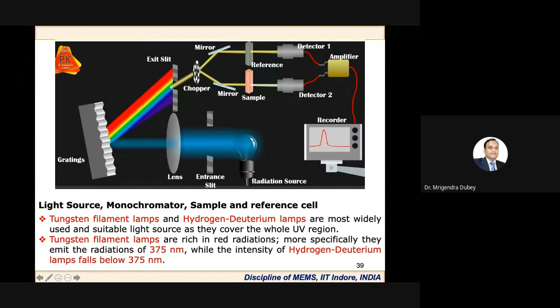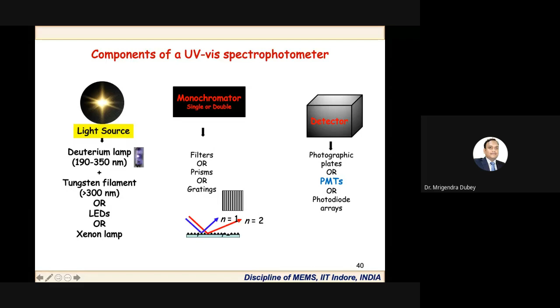So what are the components of a UV visible spectrophotometer? Typically, we need a light source, which is a deuterium lamp plus tungsten filament, or it can be an LED or a xenon lamp, depending on the setup. Next, you need the monochromator, which can be a filter, prism, or grating, as I discussed. Then you need the detector, which is a photographic plate or PMT. So the usual question is, what kind of detector does UV visible use? A PMT detector, or photodiode arrays. So this is the overview of the simplest setup of a single beam UV visible spectrophotometer.